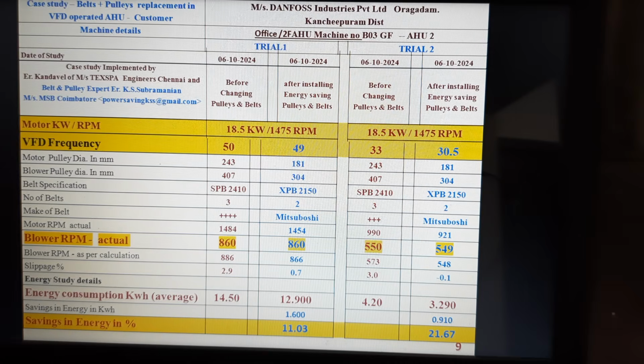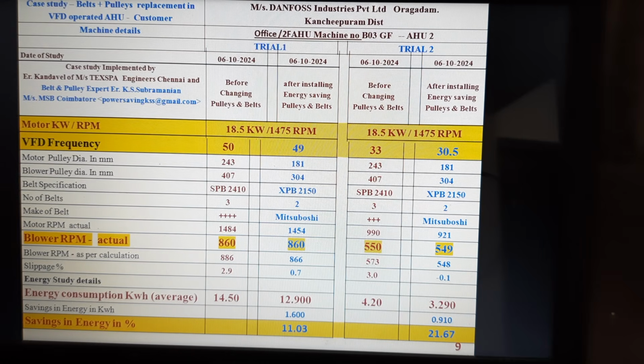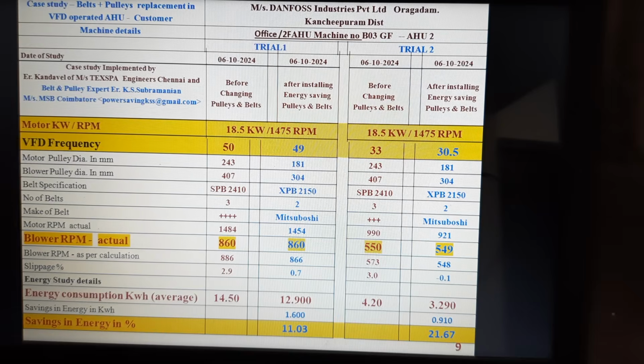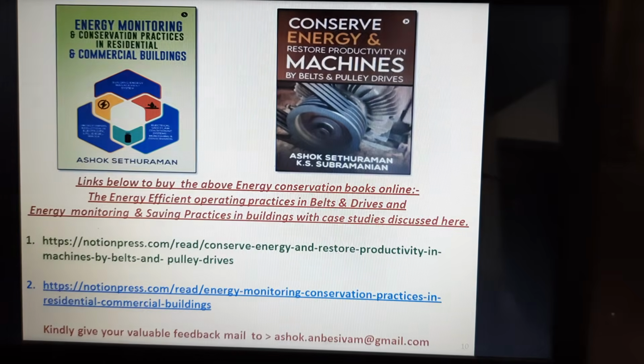They studied the day and night time usage and maintained the blower RPM at 860 RPM during the daytime. At the same 50 Hertz the blower was consuming almost 14.5 kilowatts with V-belts, and with the cogged belts it was consuming only 12.9. So around 11% was achieved from the change from V-belts to cogged belts. With redesigning of the pulleys for the VFD application, the frequency was changed from 33 Hertz to 30 Hertz, with the blower RPM maintained at 550 RPM, and here almost 22% was achieved. So you can see the energy savings possible instantly by redesigning the pulleys and belts.